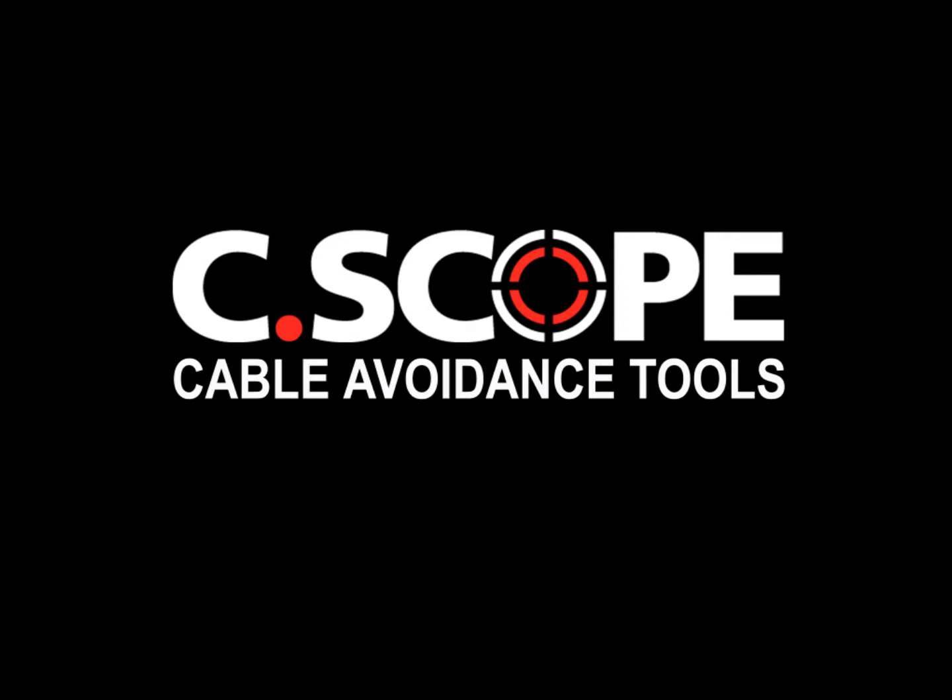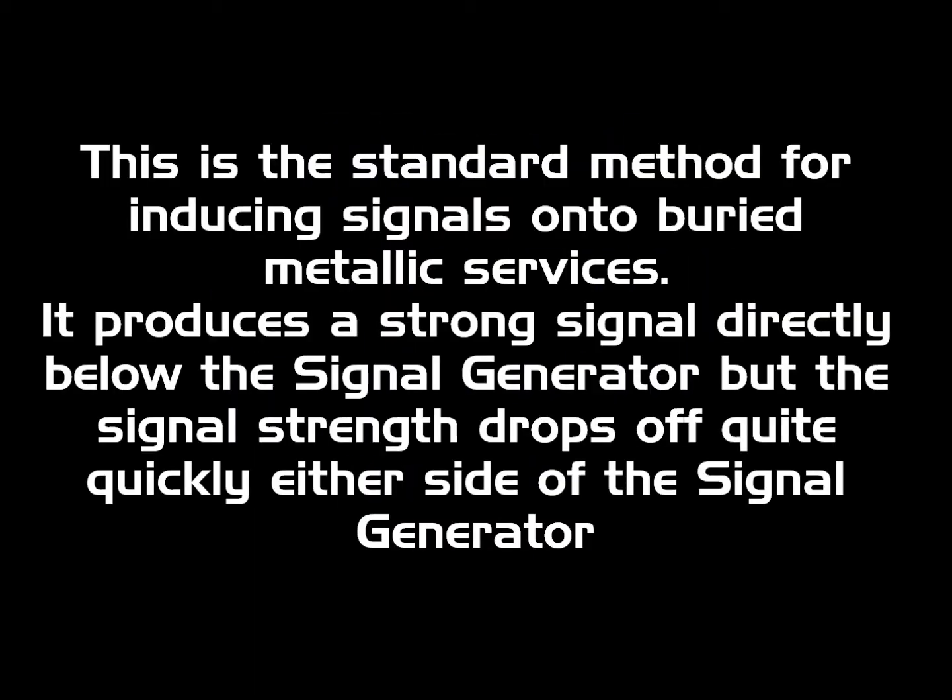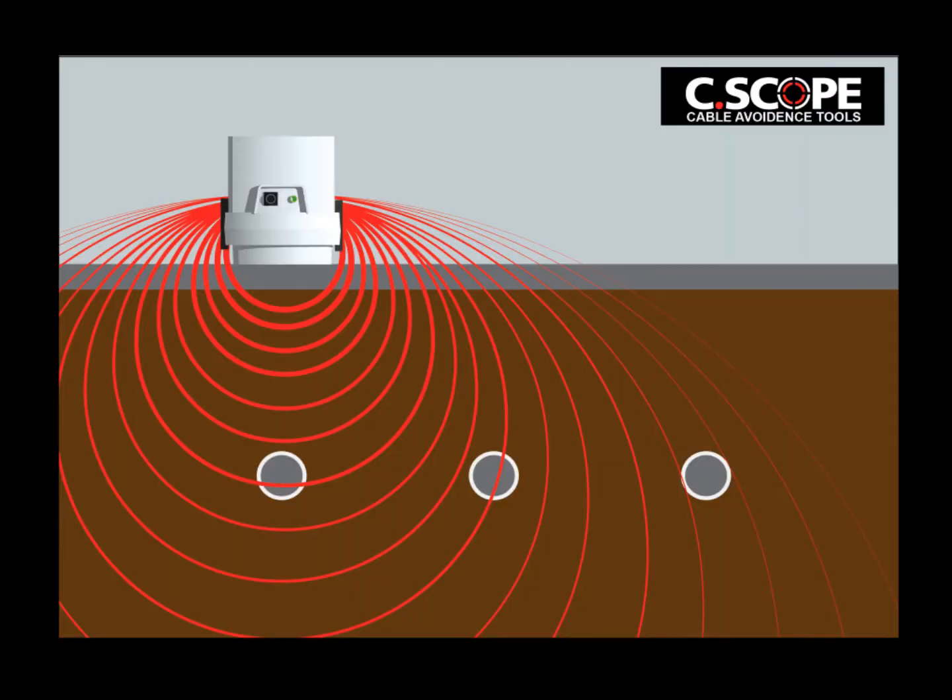C-scope Cable Avoidance Tools — Signal Generator Induction Mode. This is the standard method for inducing signals onto buried metallic services. It produces a strong signal directly below the signal generator, but the signal strength drops off quite quickly either side of the signal generator.